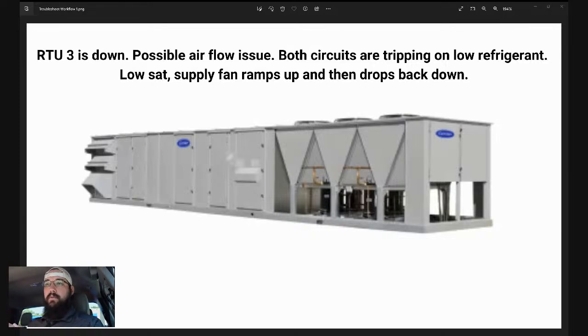Both circuits are tripping on low refrigerant. They had low saturation, and the supply fan ramps up and then drops back down at startup. So this is the call that comes in. The reason they were considering a possible airflow issue was that when the on-site engineers first went up to inspect the unit, they found the low refrigerant, or the low pressure alarm, on the touchpad.